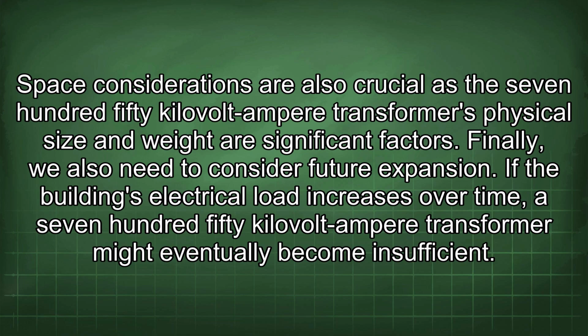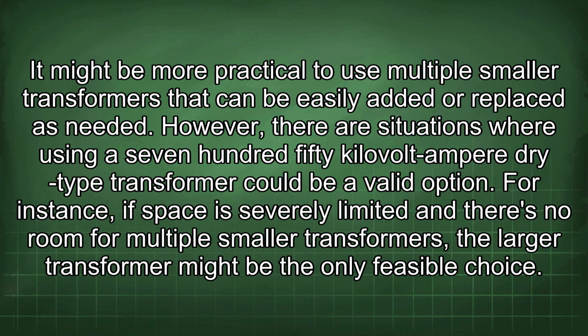Finally, we also need to consider future expansion. If the building's electrical load increases over time, a 750 kVA transformer might eventually become insufficient. It might be more practical to use multiple smaller transformers that can be easily added or replaced as needed. However, there are situations where using a 750 kVA dry-type transformer could be a valid option.